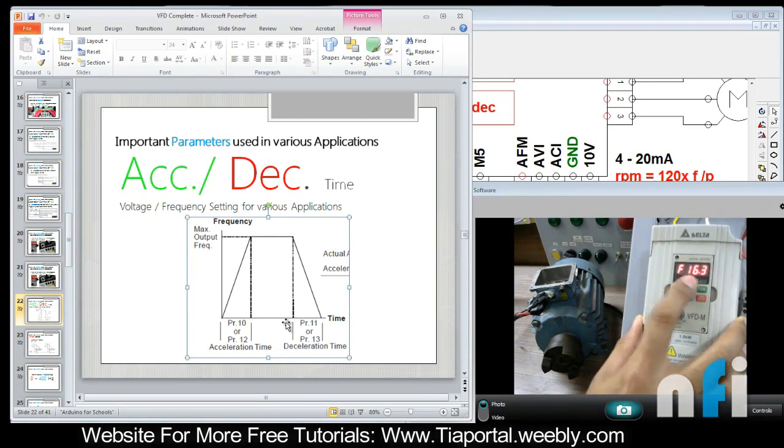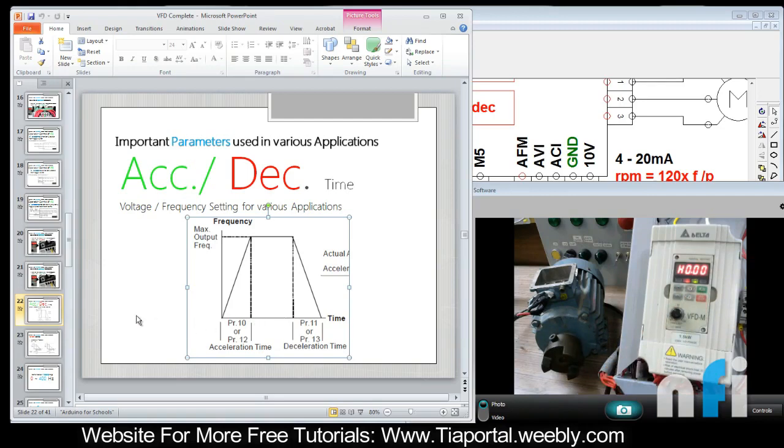Now have a look again, it's 16.3, when I run, you will find frequency will jump to 16.3 all at once, like that, motor has started immediately, when I press stop, it's stop. Run, this is the stop, this is the acceleration and deacceleration, you can change your time according to your requirements.